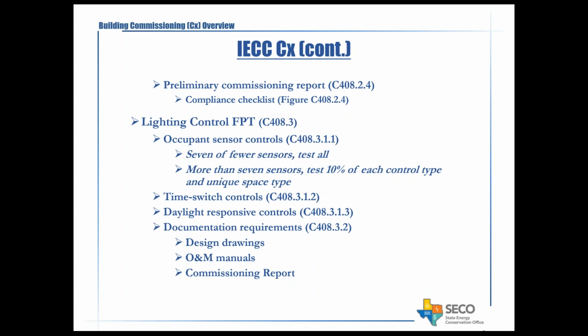If there is a time control switch, which could control the lighting through the EMS, your control system, or a dedicated lighting control system, then testing of that is required. Daylight responsiveness controls testing is required. A lot of the new codes are requiring daylight controls integrated into lighting controls, so testing of that is required, and making sure that documentation is provided for design drawings, O&M manuals, and a commissioning report is submitted for the lighting control part of it also. That is primarily what the code requires and mandates. A lot of jurisdictions are actually requiring reports, making sure that this aspect of code enforcement, which was typically not that popular or known a couple of years ago, is not ignored anymore. So that's important.